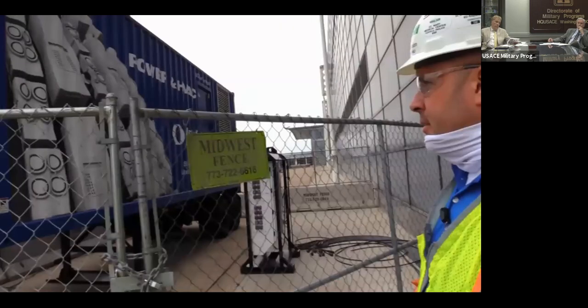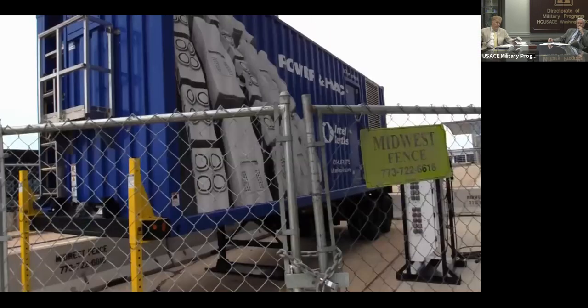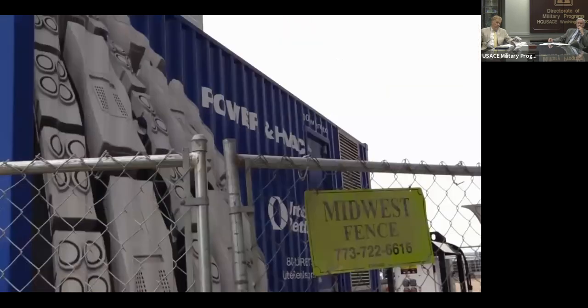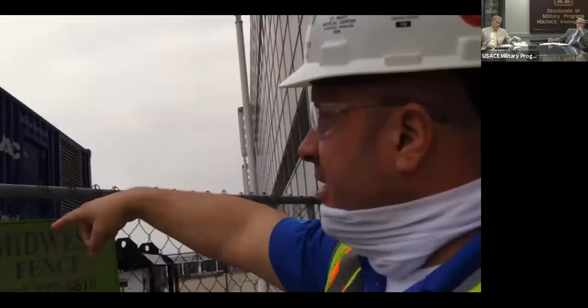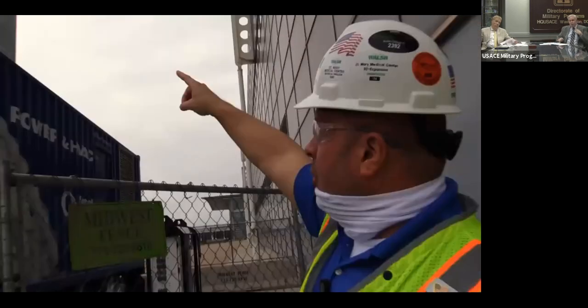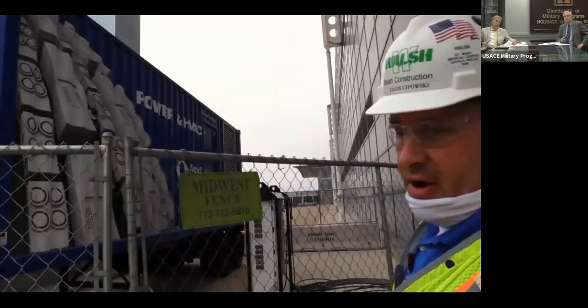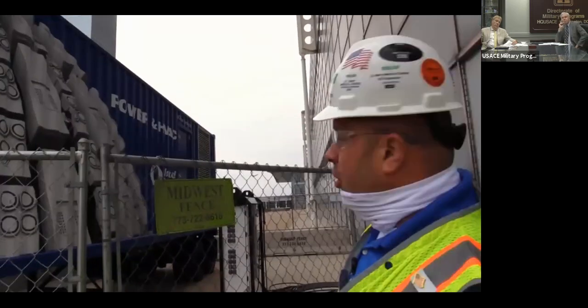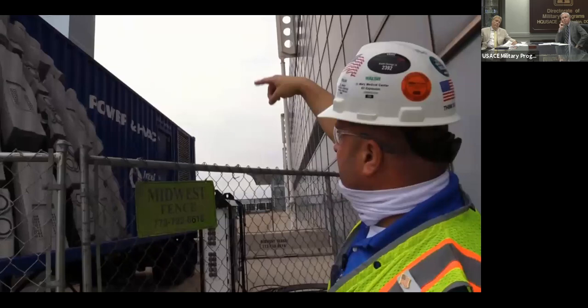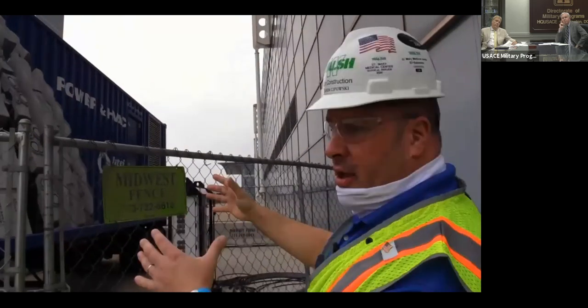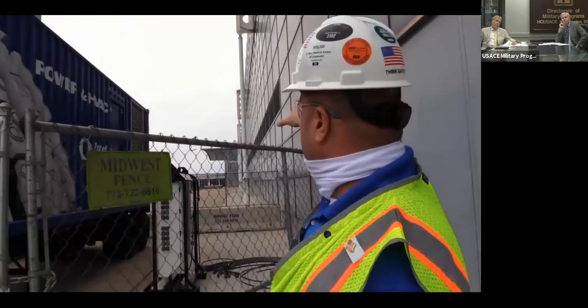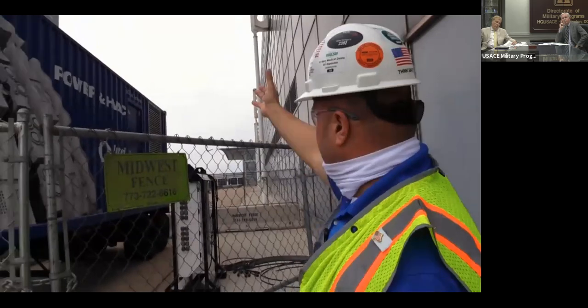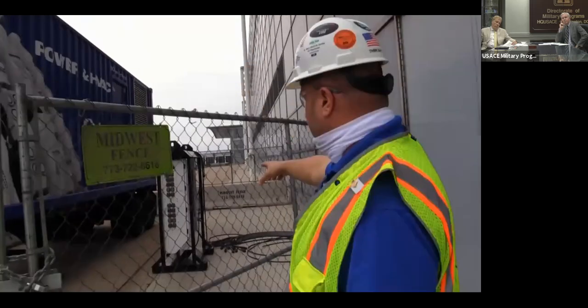We've got a generator outside here, 1,000 kW right here, that has the fuel tank inside. That ductwork on top is to exhaust it away from the fresh air intakes right there, because by code I have to keep it 20 feet away. So with that extension of the ductwork, when it's running, the exhaust will be far enough away from the fresh air intakes. All the power is distributed through that distribution panel and then through the facility.